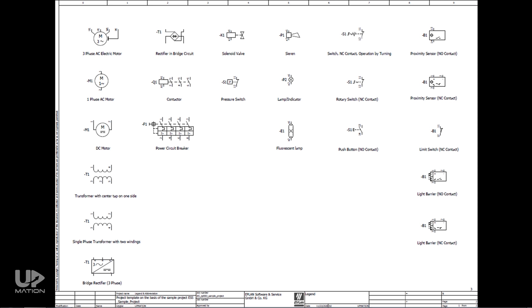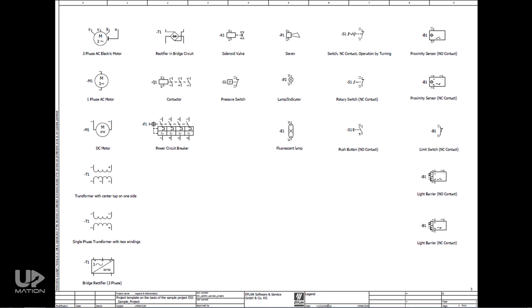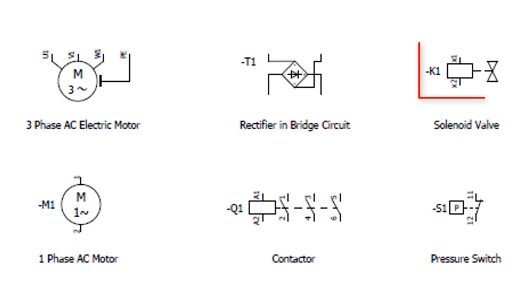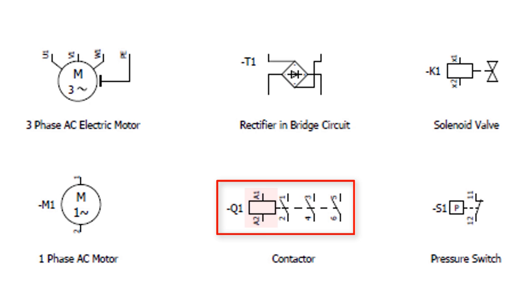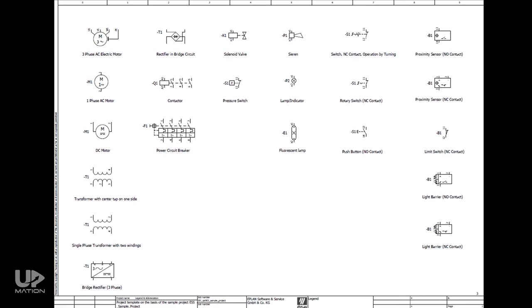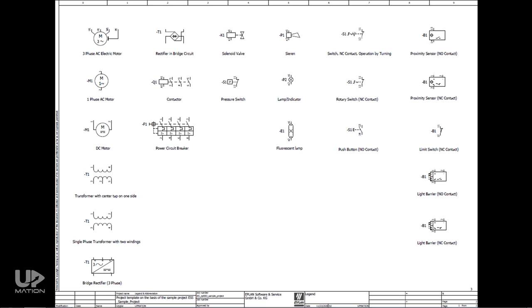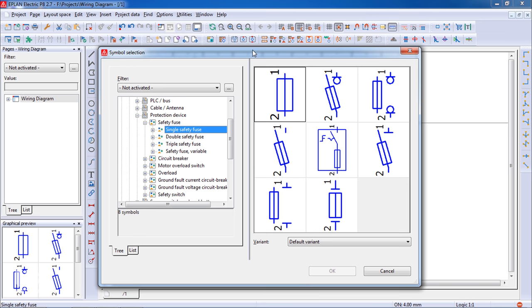Normally, the very first step to learn reading a wiring diagram is becoming familiar with the symbols of the equipment and each wiring diagram is supposed to have a page or two for this purpose. This page is known as legend and abbreviation page. To have a quick look at the symbols, you see a three-phase AC electric motor symbol here. This one is the symbol for a solenoid valve. This is a symbol for a contactor. This is the coil and these are the contacts. Remember that these symbols may have some minor differences in different wiring diagrams depending on the eCAD software they have been designed with.